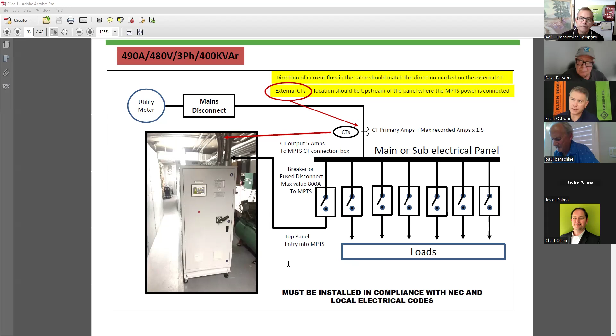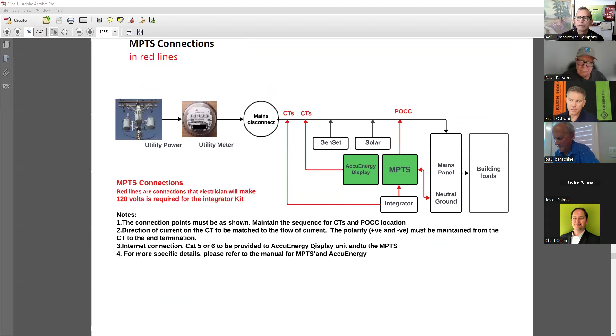So the CTs, you have actually witnessed a couple of installations of CTs in the incorrect locations, and that is why it's very important to make sure somebody's qualified to install those CTs in the correct position and properly route the CT leads to the Accu Energy. Correct. Making sure that you've got 2 sets of CTs that are going to be upstream, or on the source side, of the point of common coupling.